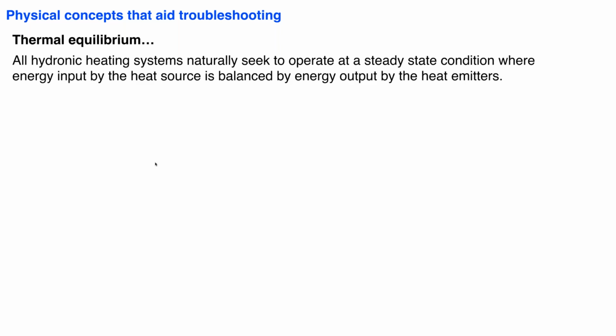If it weren't for controls, if we just turned on a hydronic system and let it find its own balance point, we may have conditions that are acceptable, or we may not have acceptable conditions based on comfort, based on safety of operation, and so forth. Thermodynamics really doesn't care about that. It just cares about that balance between energy input and energy output.